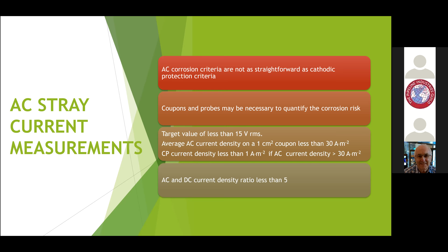There is a device called an electrical resistance probe, which has a 1 centimeter square exposed surface area. This probe works in a special way, because we know how to measure and calculate the resistance of a 1 centimeter square piece of steel. And we know there's a relationship between the resistance and the surface area.